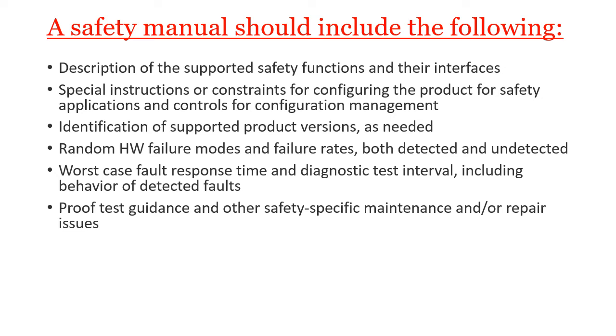Then proof test guidance. Those who are already aware of how the SIL calculations are done know that while doing the SIL calculation, we need to mention what the proof test coverage is. And this proof test coverage you will find in the safety manual. There are cases where the manufacturer provides different levels of proof test coverage depending on the action that has been performed on that particular instrument.